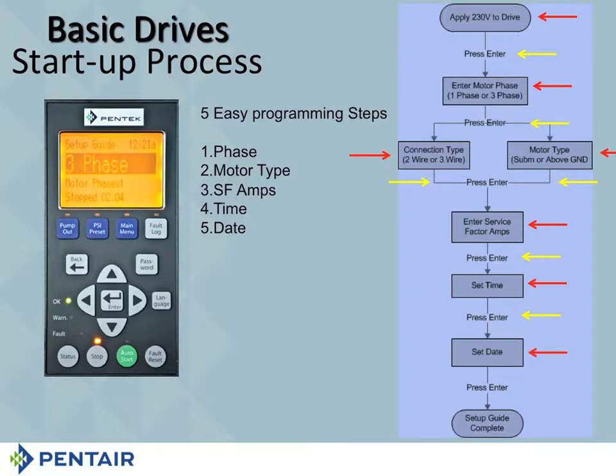It's going to ask you to set the date. If you don't take the time to set the date, if you just press enter, it'll set a date, January 1st of 2009. We're a little ways away from that. That's going to panic your customer when they see that on the fault log. So it's kind of important that you do set that time and date. All right? When you set that date and you press enter, you're done. Now I'm going to tell you right up front, if this 5-step process is not done, the drive will not start. You must at least press enter after each one of those. If you didn't enter service factor amps, you just hit enter, it's going to stay at 0 and it'll say, fine, I'm going to run this pump at 0 amps. Now you know how much work you're going to get at 0 amps, don't you?